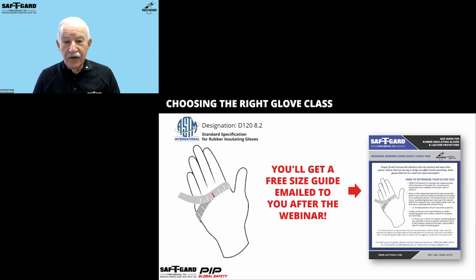Now, once you've chosen that right glove class, you take care to choose the right size, because proper fit will ensure the likelihood that the workers will wear the gloves. Rubber gloves that are too big or bulky can affect tactile sensitivity, while rubber gloves that are too small can cause discomfort. I'll refer again to ASTM D120, section 8.2, which indicates the measurements on the diameter of the palm for manufacturers, measured at the midpoint of the palm plus or minus a half inch, as you can see on the screen. So you measure the hand by wrapping a tape around the palm. This number will generally equate to the probable size of the rubber insulating glove to select. Personal preference for tightness and finger length will ultimately determine the size that the wearer will choose, but it's got to fit right.